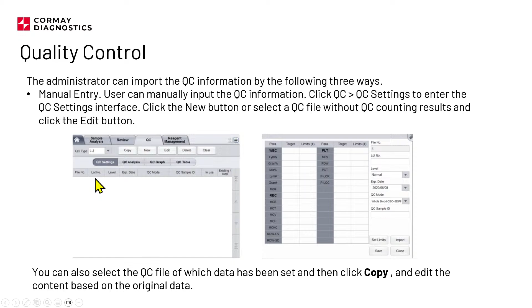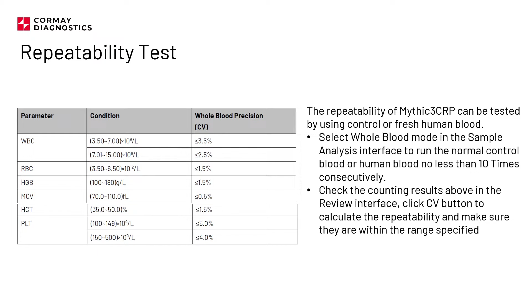Yeah, and I believe it's explained here in the same way. Repeatability test. The repeatability test can tell you a lot of things about the analyzer, and we also recommend performing this test during the first installation of the analyzer.